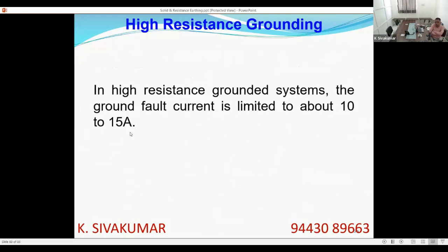As I said, core damage minimization. So in high resistance grounded system, the ground fault current is limited to about 10 to 15 ampere. This is the general guideline. But generally you go as per the core damage curve given by the rotating machine manufacturer in your system. Go by the guideline given by the equipment manufacturer.